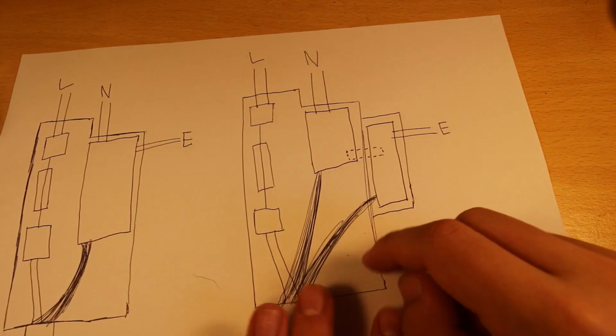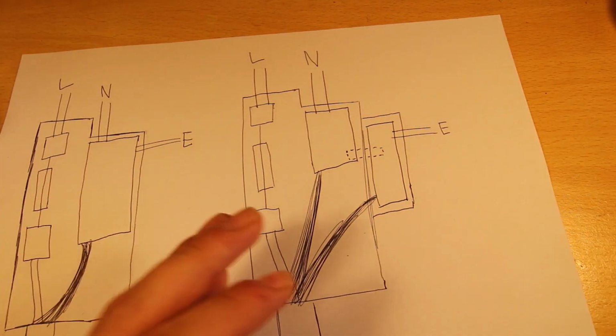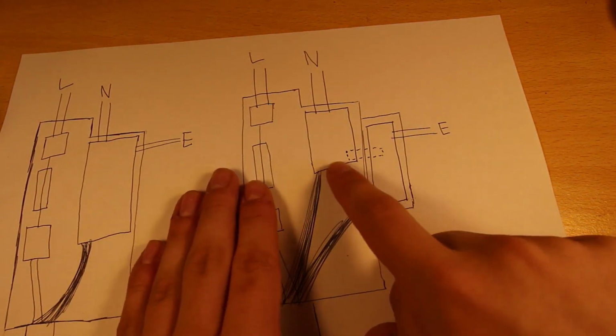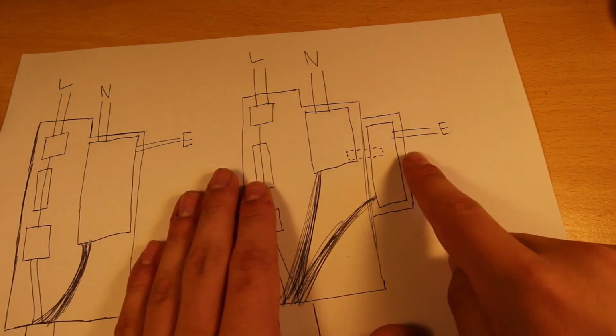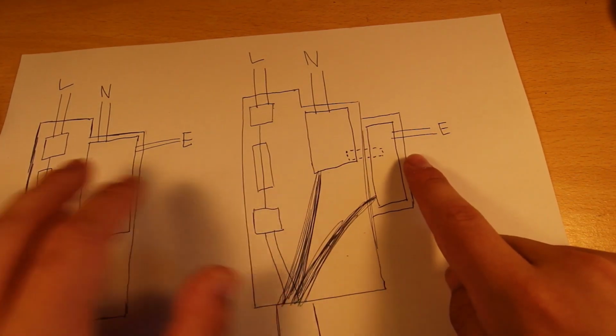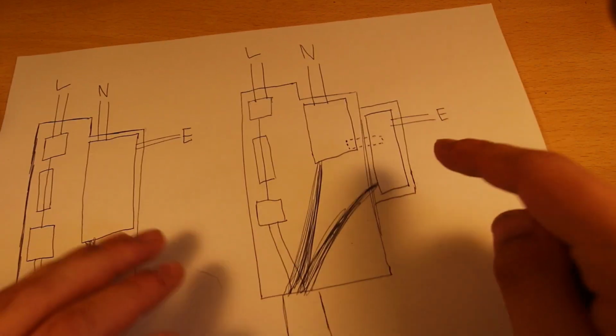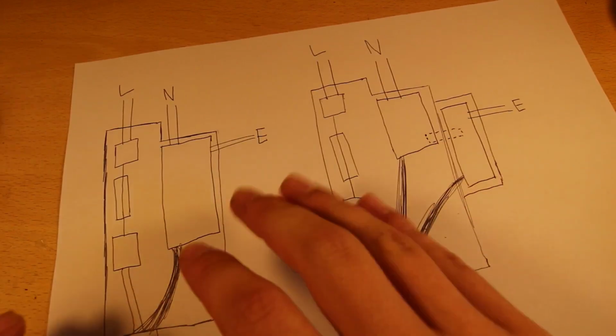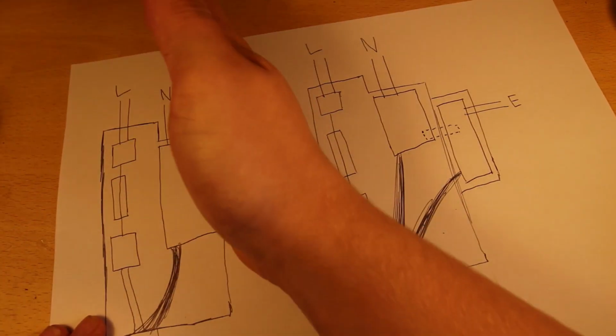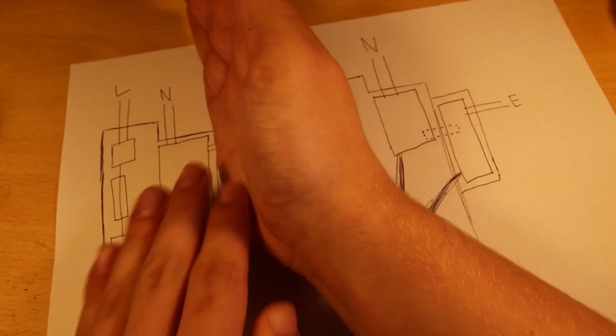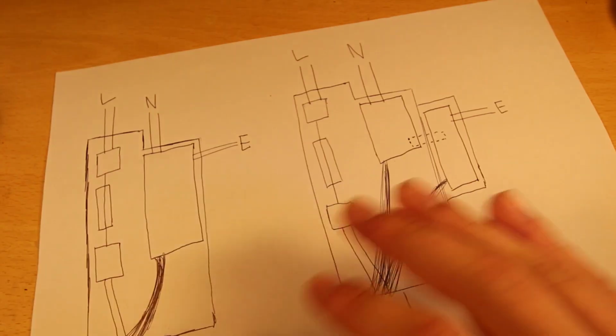Some of them are so-called adaptable service heads, so they have a link you can install here, so it makes it basically into this TNCS, and on a TT application they would use this service head, but they just block off that hole at the side, so you have a live and neutral come out and no earth provided by the network operator.